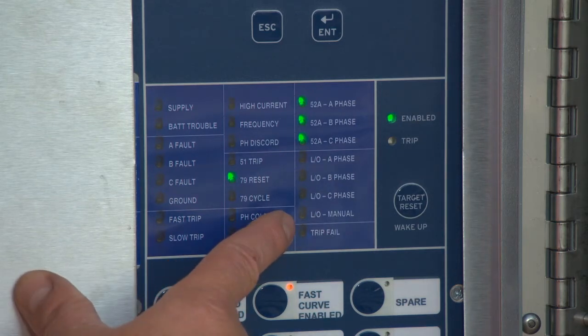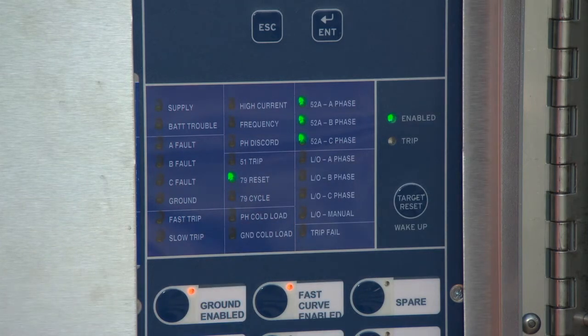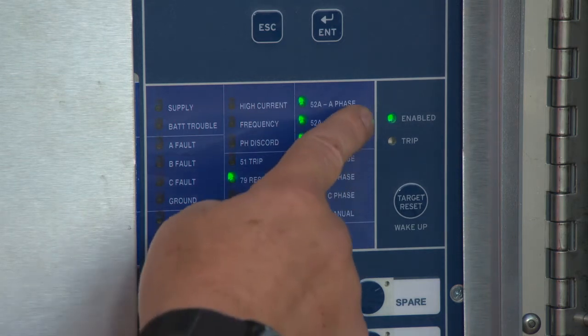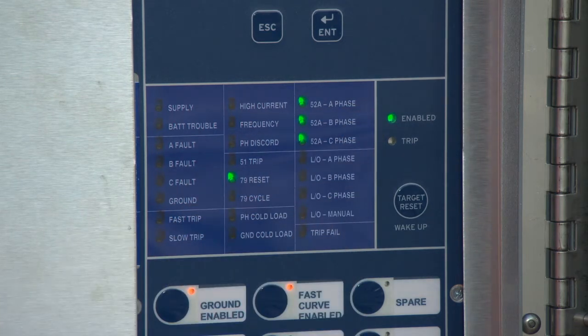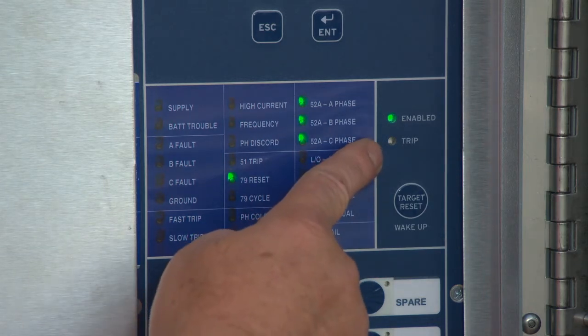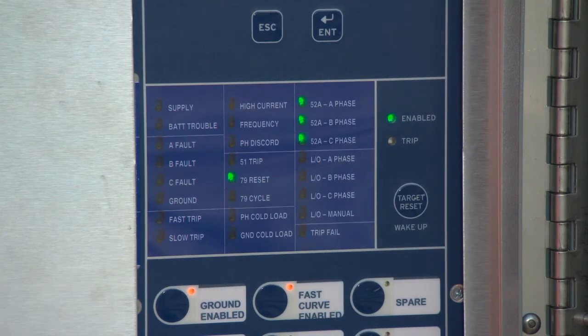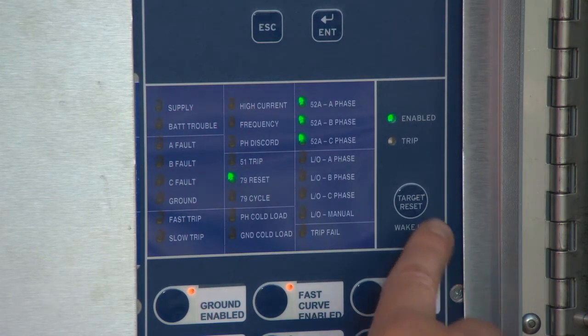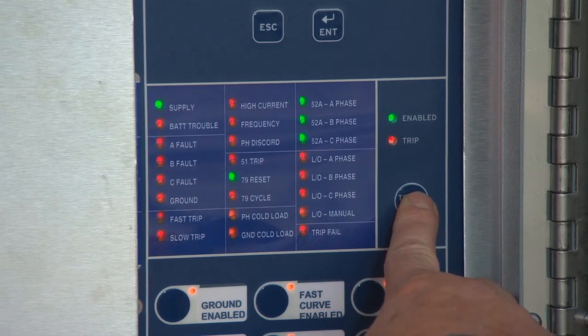LO manual. This LED will turn amber should the manual handle fall or be pulled down on one of the reclosers. Trip fail. Should the recloser fail to operate, this LED indicator will illuminate red. On the far right side is the green enabled indicator LED. This tells us the unit is enabled and ready to function. The trip LED will turn red if the recloser trips out. Finally, the target reset button will test all LEDs and reset the target conditions.